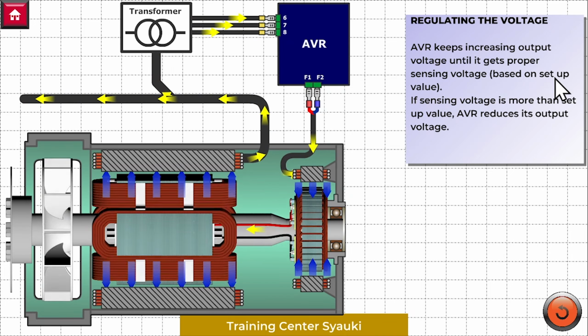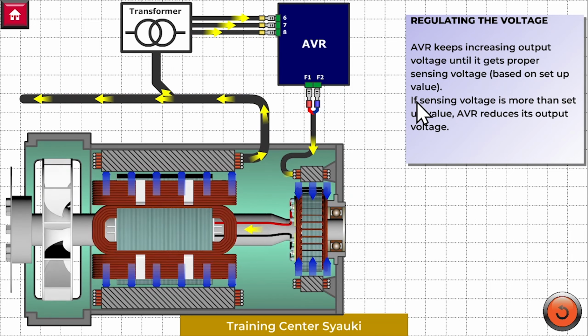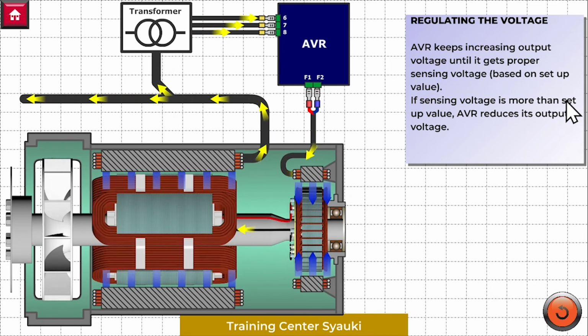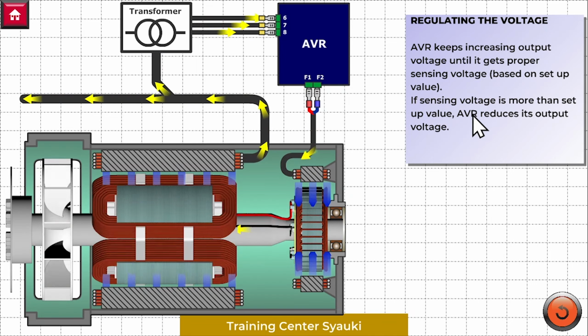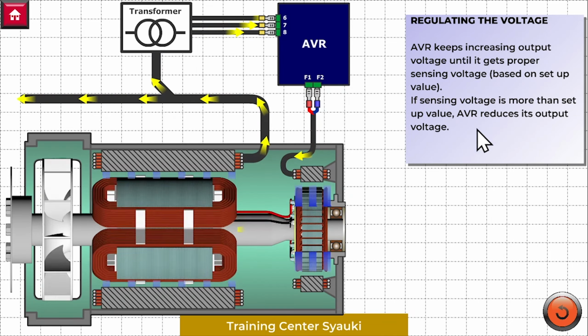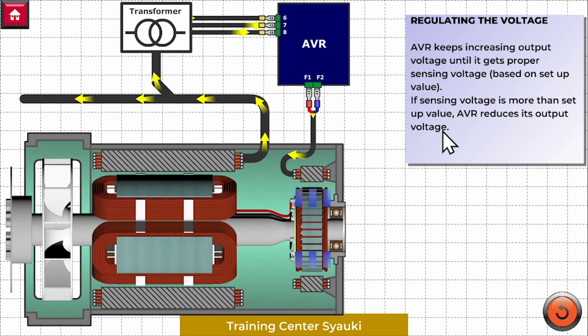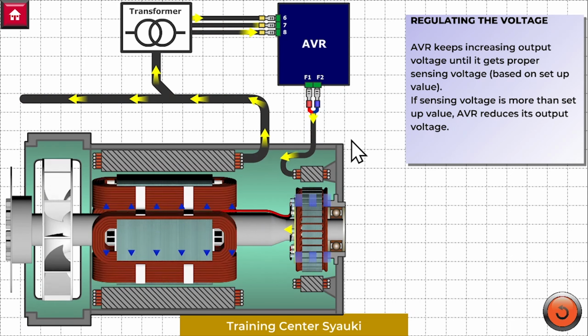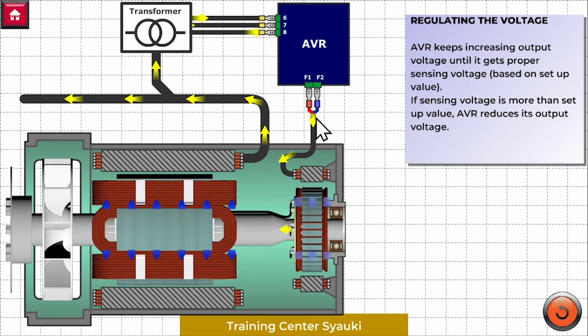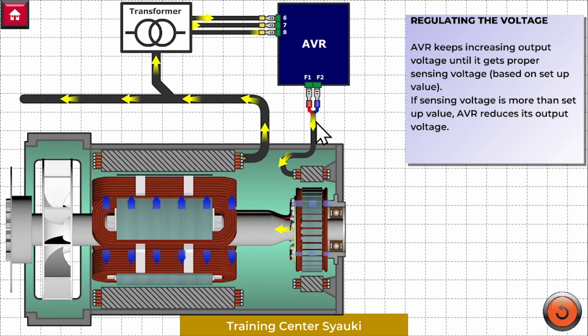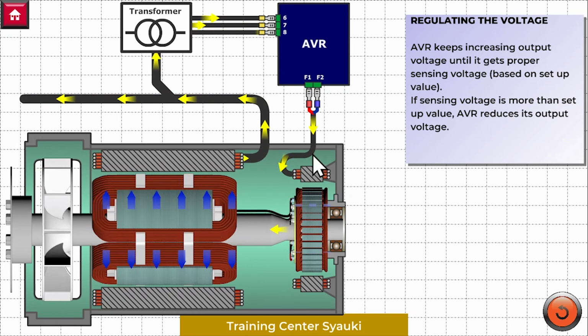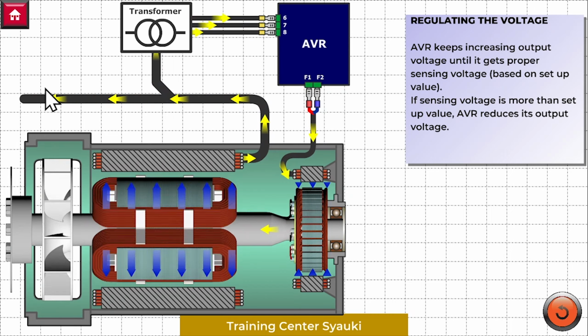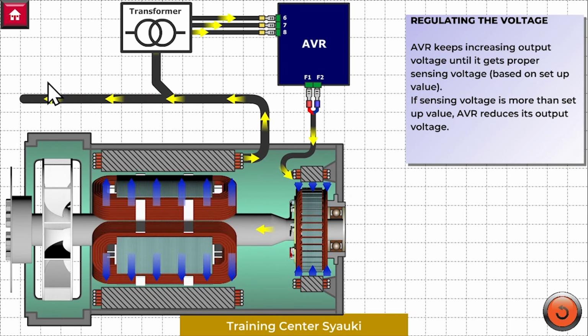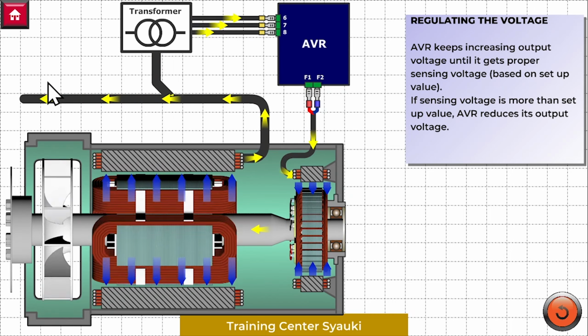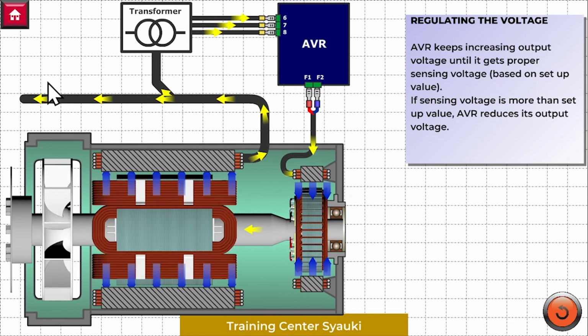It is based on the setup value. If sensing voltage is more than the setup value, the AVR reduces its output voltage. As I said before, normally it needs around 8 to 12 volt DC to achieve output of 380 volt AC in no-load condition.